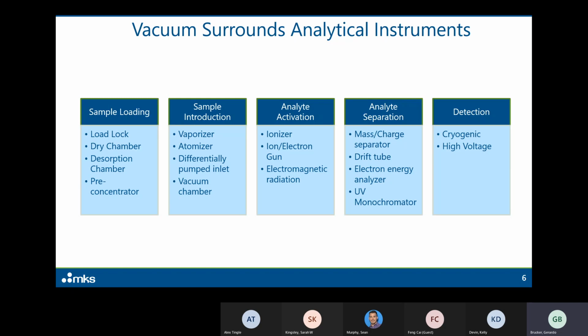From the analyte activation block, we go to the analyte separation block. This is where we have the ions now, or the photons that we are interested in. Now we have to separate those analytes so that we can do the qualitative and quantitative analysis. This could be the mass-to-charge separator in a mass spectrometer, in which case I need vacuum to make sure again that the ions don't get lost to neutral collisions, or I might actually need to control the vacuum to make sure that I have collisions that allow me to do, for example, collision induced dissociation. This could also be a drift tube in an ion mobility spectrometer. It could be the electron energy analyzer in a microscopy system, or it could be the inside of a UV monochromator.